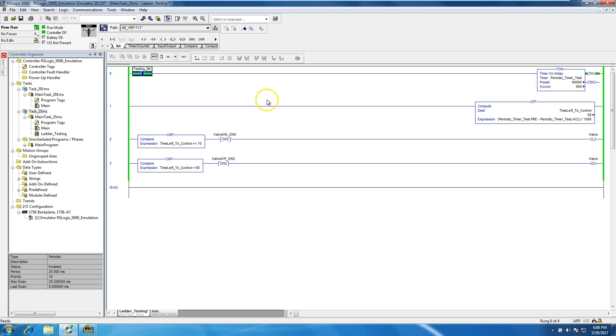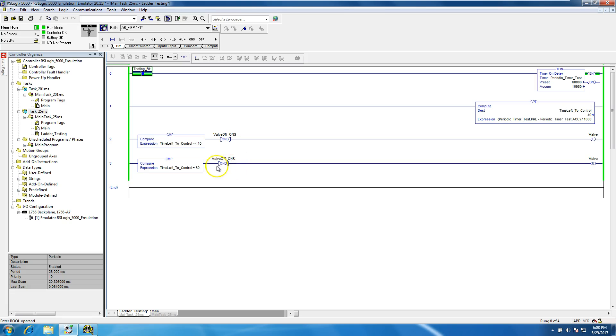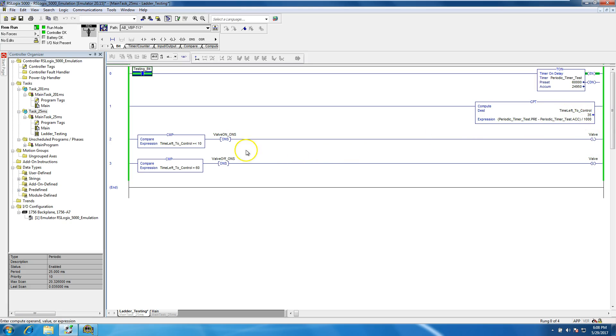Right now neither one of them are on. The time left is equal to 60 so it's not triggering, and it's not using a one-shot. The time left is not less than or equal to 10 seconds so it's not cutting the valve on. Once the time left reaches 10 seconds or below, it will cut the valve on.